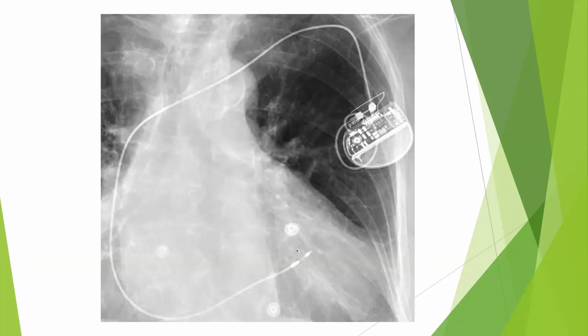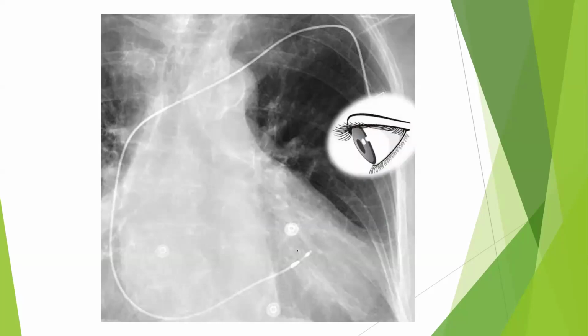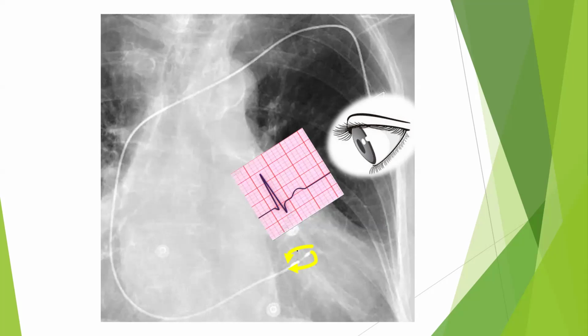Yes. Okay, if I told you the main job of the pacemaker is actually to watch what the heart is doing. And based on that, we'll decide what's the next step. So basically, it monitors that through the intrinsic polarity of the lead tip to the ring. And that's what we call sensing. And as a result, if it sees a QRS, it will do nothing. If it doesn't see a QRS, it will pace them.